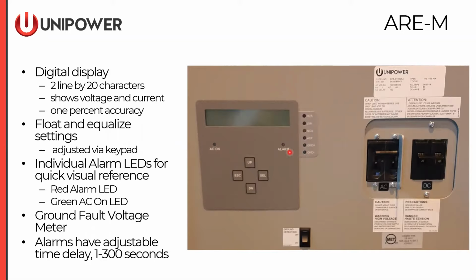And you have a green AC LED that, as long as AC service is present, the green LED is illuminated. You also have all chargers equipped with a ground fault detection circuit that displays the level of severity of ground fault using the front panel menus and keypad. All available alarms have an adjustable time delay. So the default is 5 seconds, and that can be adjusted all the way up to 300 seconds or down to 1 second if necessary. Next slide.